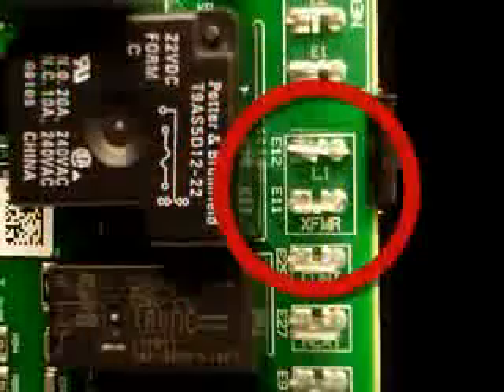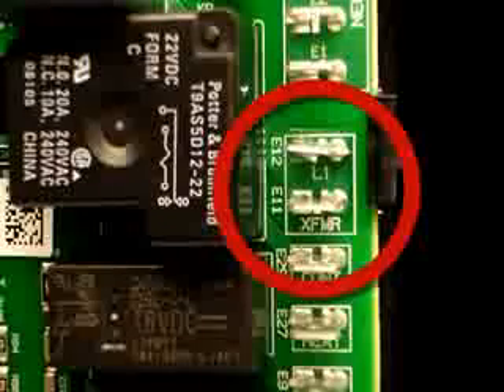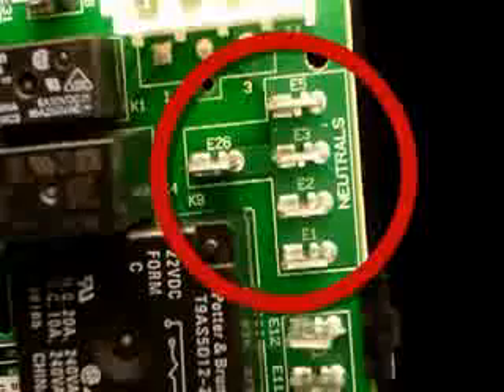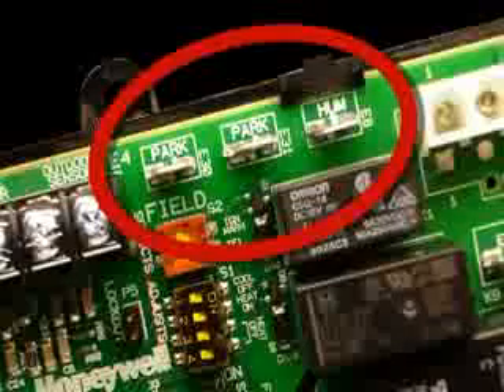line voltage output to the transformer, and a place to power an electronic air cleaner, as well as the 120 line voltage input. 5 neutral terminals are provided to make it convenient to connect up all the line voltage circuits. This plug sends power to the inducer motor and the line voltage hot surface igniter. These terminals are for the humidifier and dummy terminals to park unused blower motor leads.